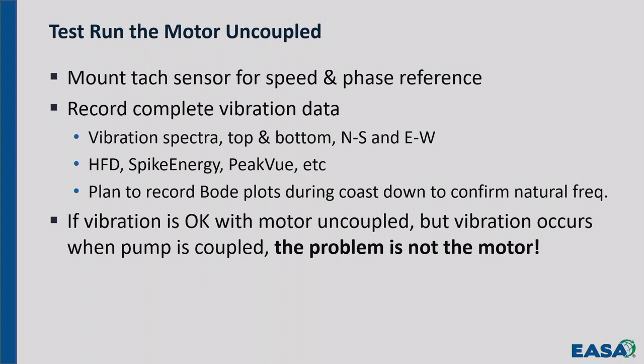This is important. You run the motor uncoupled. You're going to check direction of rotation. You want to do this start up and coast down. Okay? So you run the motor uncoupled, and then you couple the pump up, and then it vibrates. The problem's not the motor. Okay? Does that make sense?